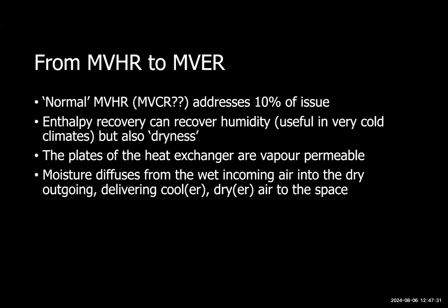But that's only about 10% of the problem, as we saw in that pie chart earlier. Enthalpy recovery works by having vapor-permeable membranes or panels inside our plate heat exchanger, so moisture can pass from one airstream to the other. That's helpful in very cold climates like Canada, but we can also recover dryness, which is what we're interested in here. Moisture is transferred from the over-moist incoming air into the dry outgoing air, so we dry out our incoming air, which is what we want.